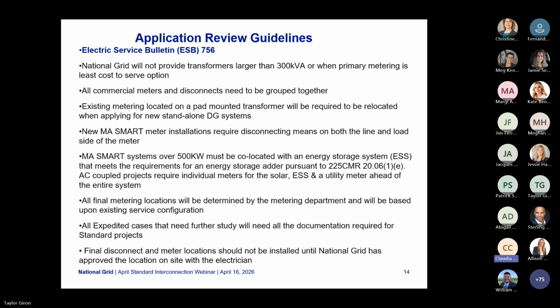An existing meter located on a pad-mounted transformer would be required to be relocated when applying for a new standalone DG system. New MA smart meter installations require disconnecting means on both the line and load side of the meter. A new MA smart system over 500 kW must be co-located with the energy storage system (ESS) that meets the requirements for the energy storage system adder. AC coupled projects require individual meters for the solar and ESS, and a utility meter ahead of the entire system. All final metering locations will be determined by the metering department and based on existing service configurations.